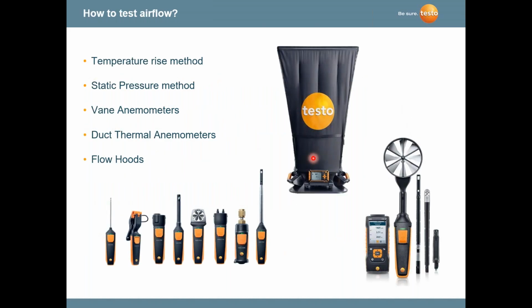We have a whole seminar just devoted to airflow because it can get complicated, just like anything else in HVAC. But there are instruments out there that measure airflow, and we can do it with a lot of different methods. We can use the temperature rise method. We can look at static pressure through a differential manometer. We have a lot of different vane anemometers. We have duct thermal anemometers that go inside the hard ducts to measure airflow, and we can convert that to CFM. And we also have flow hoods, which are used a lot by mechanical contractors for test and balance.